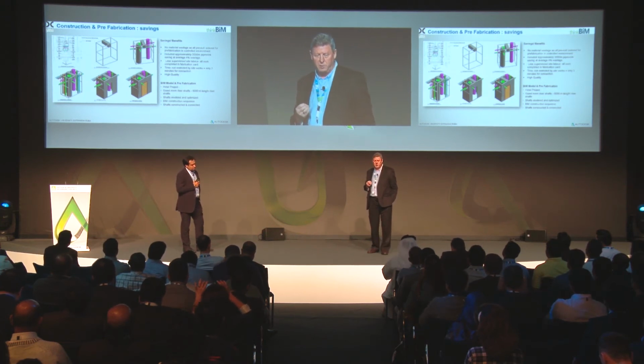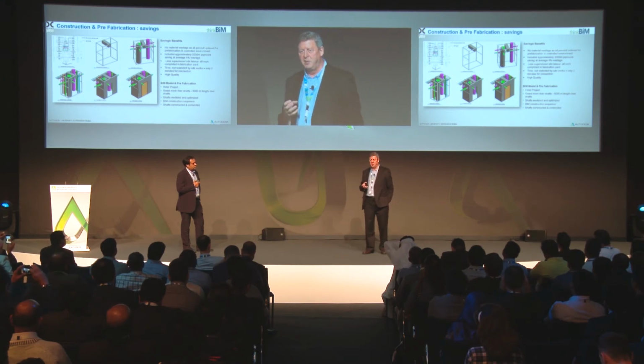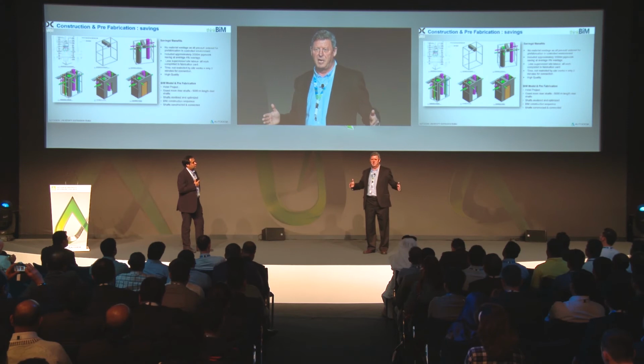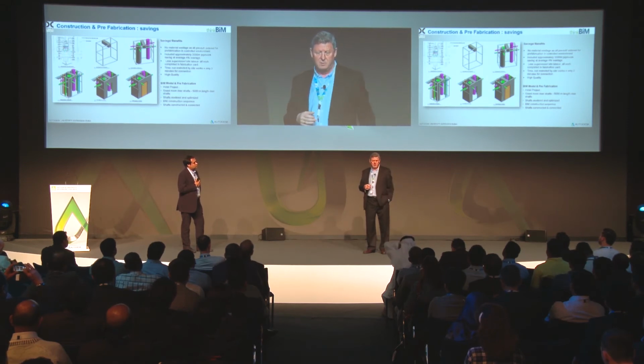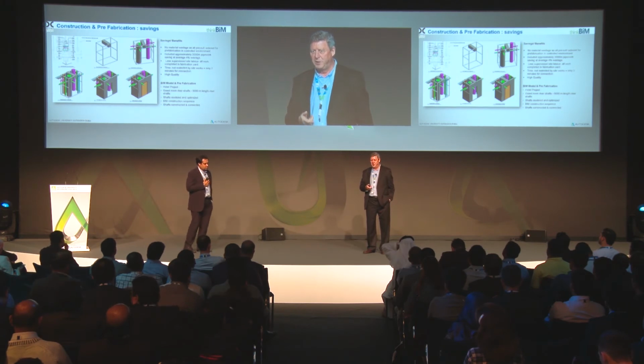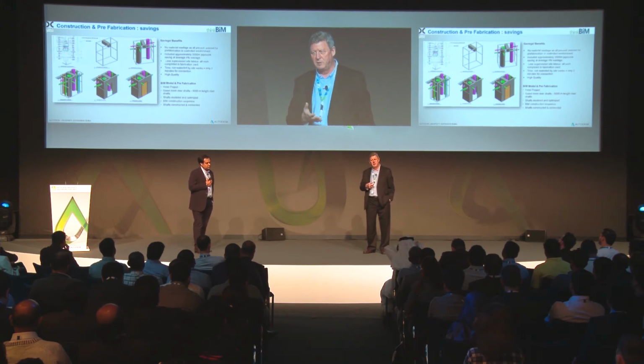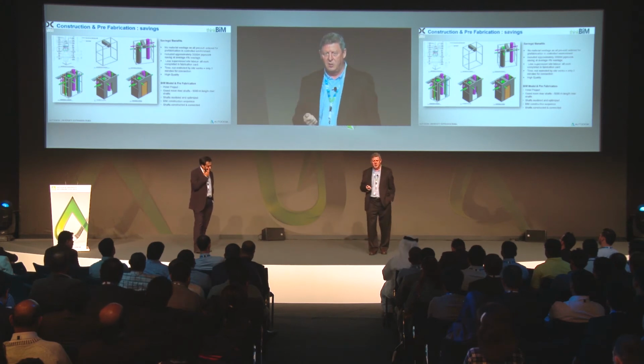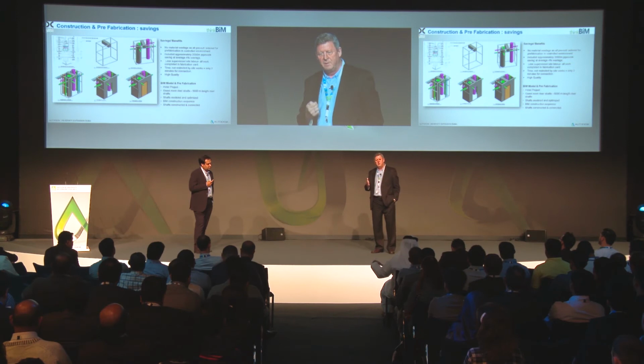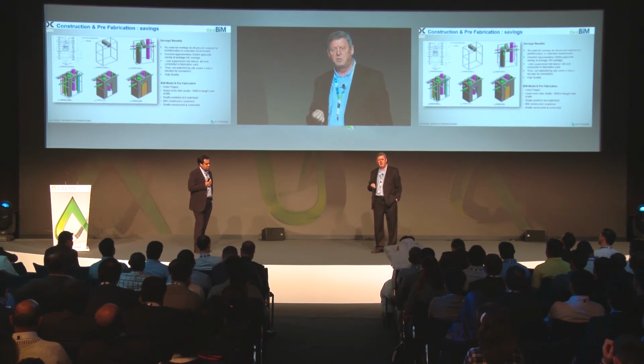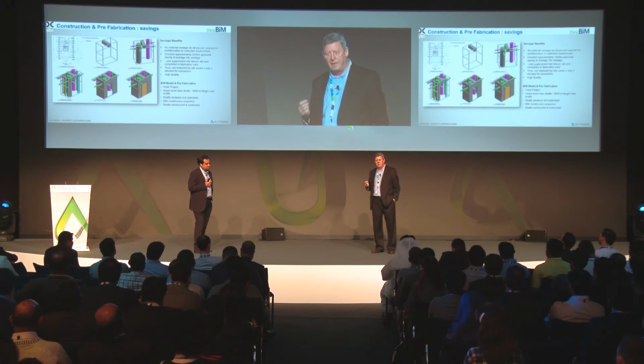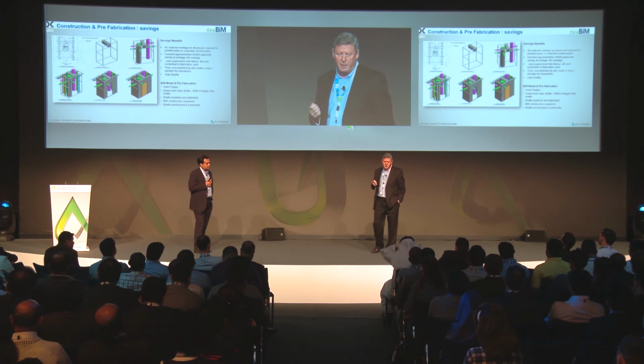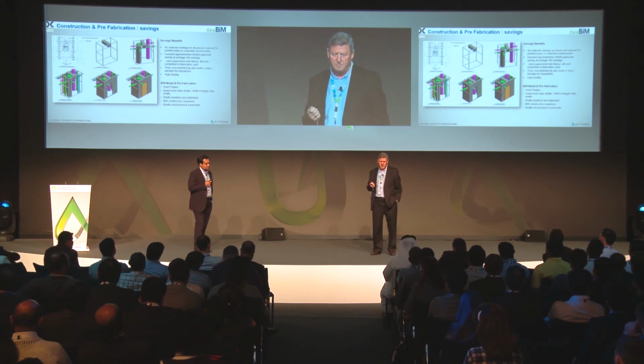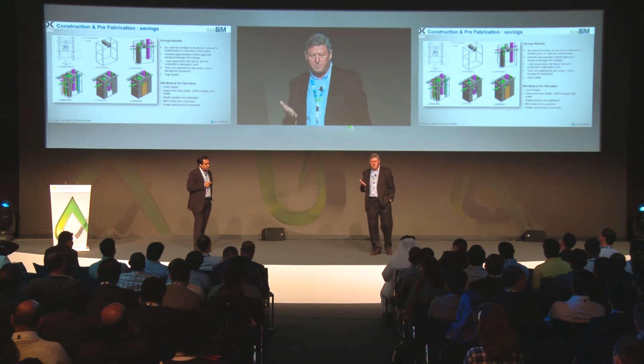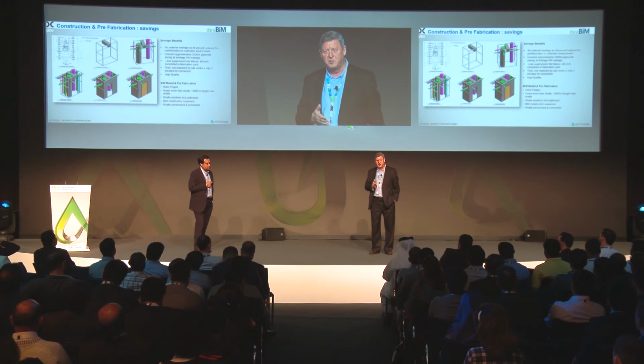The contractor wanted us to use circular ductwork, which is rare because risers are typically sized for wide and narrow ducts. Doing this exercise on a 2D drawing would be almost impossible, but by creating a 3D BIM model we managed to accommodate circular ducts—cheaper, more efficient, less cost, fewer joints, easier to make. We were also able to move pipes within the riser and optimise pipe length, using standard lengths with no offcuts, saving about 2 kilometres of pipework. This also saved a massive amount of construction time since it could all be built off-site.